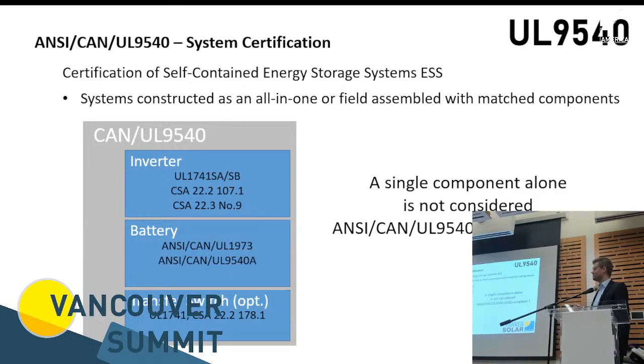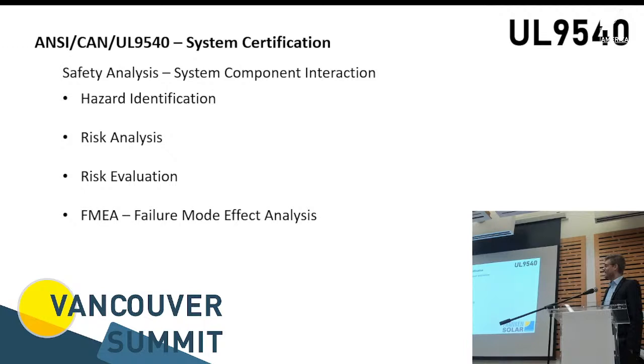And that's very important because that is a relatively new thing. With that new harmonized code, so the CAN for the Canadian market, the UL for the US market, the 9540 to the 2020 version, which is the newest one, which is now required under CEC 2021. We no longer talk about individual components. We always talk about the entire system. At the end of the day, coming back to my first statement, it's all about safety.